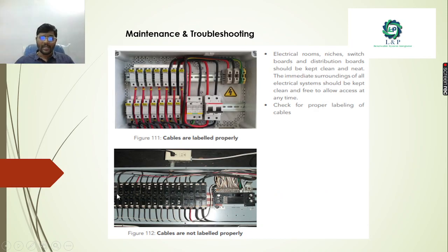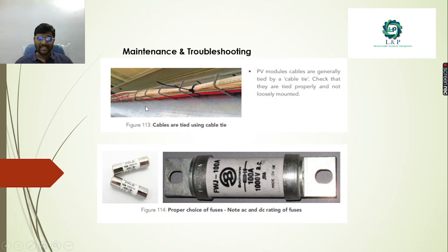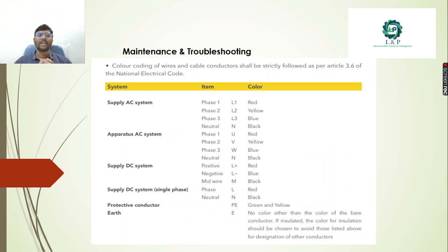Make sure the cables are labeled properly, because this is useful for maintenance. If they are not labeled, it is very difficult to trace which cable is coming from where. Always use cable labeling, which is very important on the panel side. Make sure your PV cables are routed properly using cable ties, and always make proper choices of fuses. Use AC fuses for the AC side and DC rated fuses for the DC side. And most importantly, when you are performing wiring, always ensure you follow the color codes.